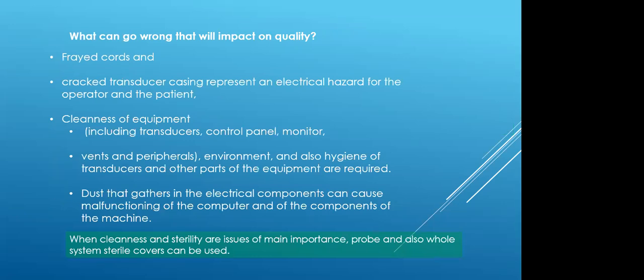Now, this is what I've just touched here and there as I was going. What can go wrong that will impact on your quality, right? One of the biggest things that happens with ultrasound equipment is frayed cords. And then, of course, sometimes people knock transducers or drop them. So you have cracked transducer casings, which are an electrical hazard to the patient and the operator.